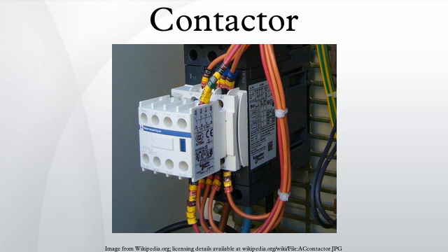For contactors energized with alternating current, a small part of the core is surrounded with a shading coil, which slightly delays the magnetic flux in the core. The effect is to average out the alternating pull of the magnetic field and so prevent the core from buzzing at twice line frequency.